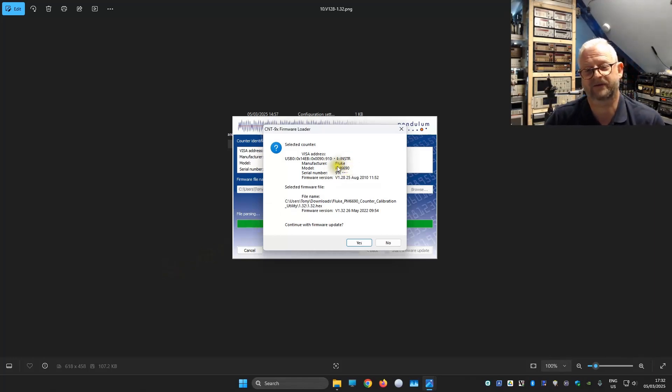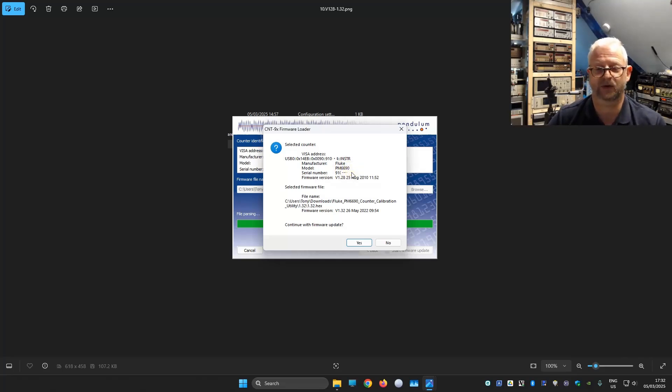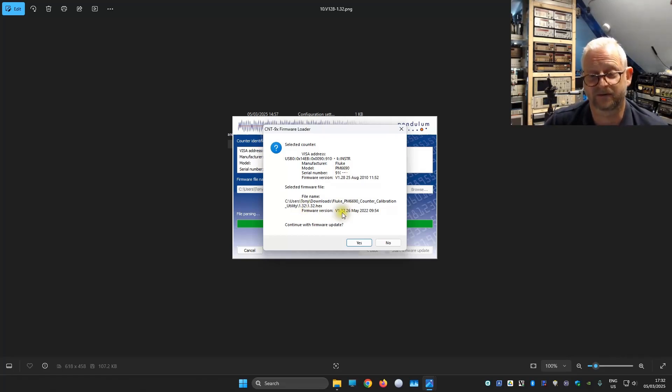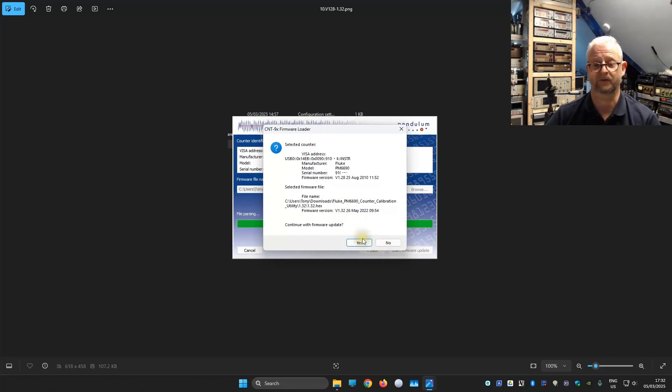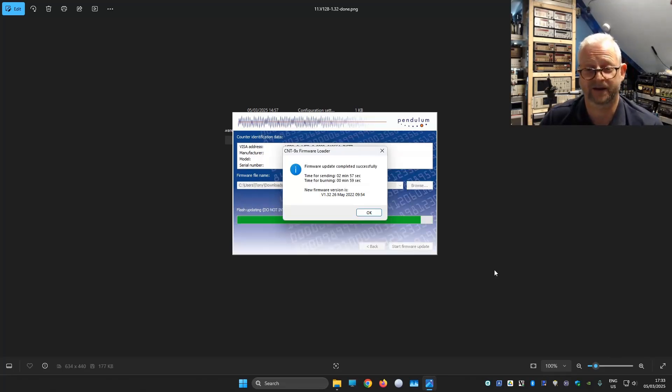I'm starting exactly the same uploader that I used for the 1.28. And here we can see it still thinks it's a Fluke. So that is good. So the uploader is really for both models or all three brands. And here we can see it detected correctly 1.32. So we push the yes button. And we go again.